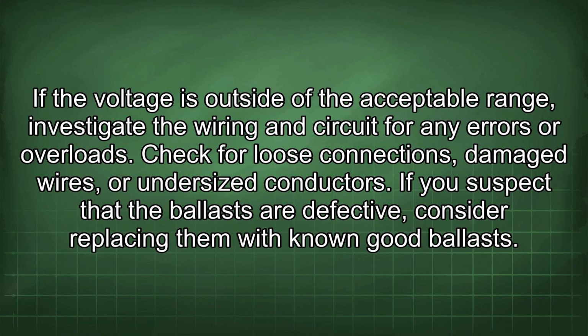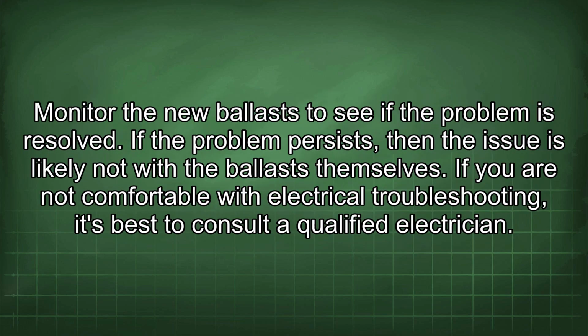If the voltage is outside of the acceptable range, investigate the wiring and circuit for any errors or overloads. Check for loose connections, damaged wires, or undersized conductors. If you suspect that the ballasts are defective, consider replacing them with known good ballasts. Monitor the new ballasts to see if the problem is resolved. If the problem persists, then the issue is likely not with the ballasts themselves.